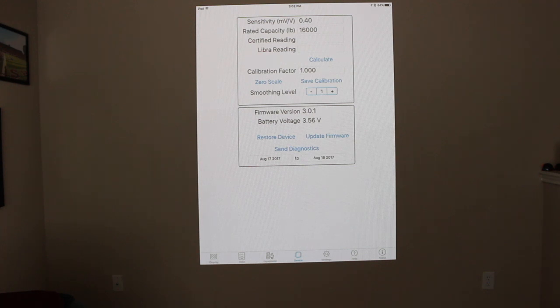When you use the 0.4 method, it allows you to use this as a cal number. So think in terms of a calibration number that you put into your scale head. This changes everything, so it makes it simple. If you look at your bars, and if you have a sensitivity on the bars, you could go through and try to figure out your rated capacity, but a lot of times that information is missing. So I say go with this method and look at this chart that we have on our app, or we'd provide this information for you either through the phone or through our app, or on a website called librahelp.com.